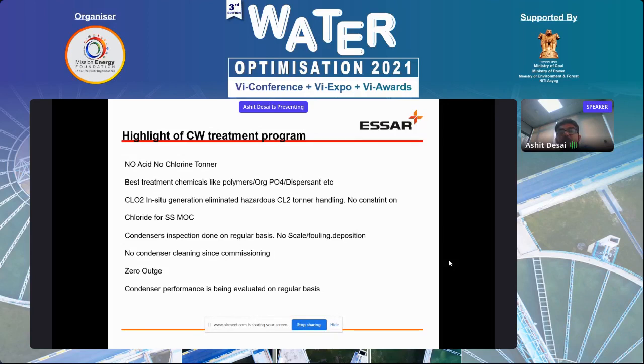Because chlorine dioxide in situ generation is implemented, there is no concern about chloride for stainless steel MOC. As per industry standard, a maximum of 270 to 300 ppm of chloride is maintained in circulating water. If you dose chlorine gas, then 1 kg of chlorine gas will contribute 1 ppm of chloride, whereas ClO2 will remain as ClO2 and will not contribute to any chloride generation. That's the biggest advantage. It's a costly affair, but it is justifiable because acid cost and chlorine cost will nullify the cost of chlorine dioxide.